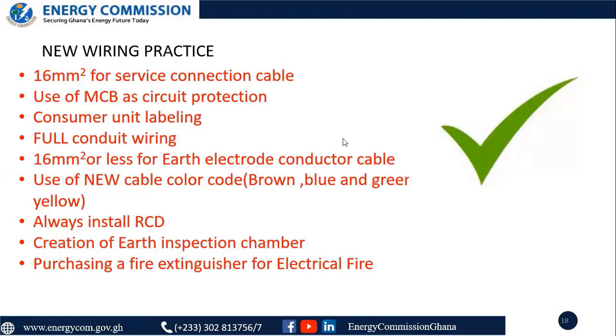And your cable's current capacity should match the load, or the cable that is bringing power into your system should be able to match the loads being used in the facility. So a 16 system will cater for all those things, because 16 readily allows these currents to pass through, but the 10 won't. Once the currents being drawn from these loads are very high, it puts burden and stress on this cable, which is 10 millimeters square, rather than the 16, which will be able to handle it perfectly.